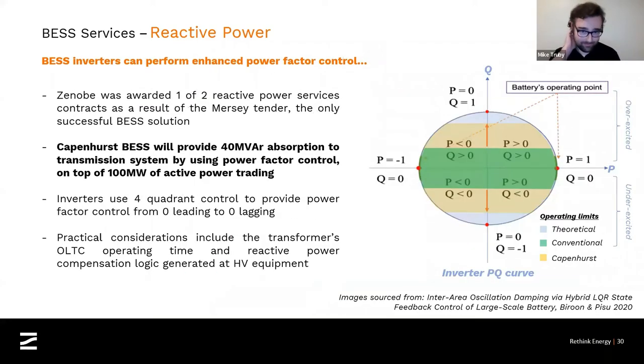Next slide, please, Simon. I've talked a bit about what that reactive power service is, but I'd like to talk about how it actually works and what happens at Capenhurst. As you've already mentioned, the battery energy storage system includes a number of inverters. We're talking in the region of 30 inverter modules for Capenhurst, and Capenhurst is contracted to provide 40 MVArs of reactive power absorption from the transmission system.